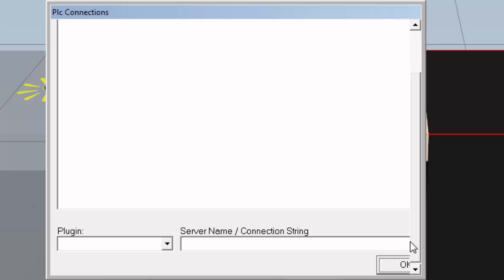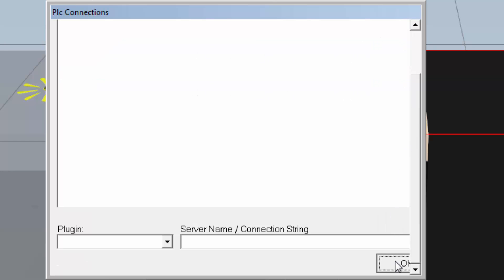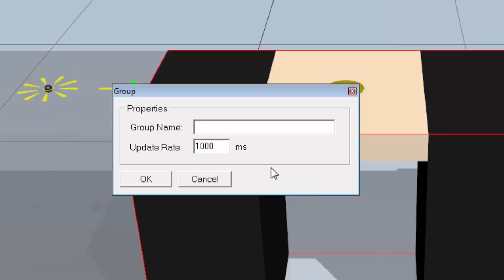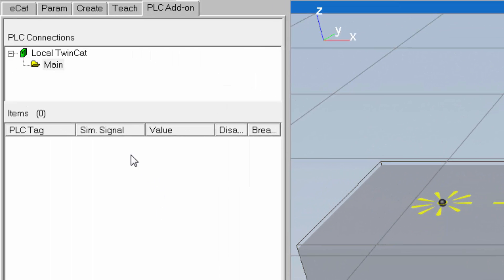I can manually type in the connection or select it from a list. I already have TwinCAT installed locally on my device, and there's the port 851. I'll scroll down and click OK. I'll give the connection a group name — I'll type 'main' — and set an update rate of 10 milliseconds, then click OK. You'll be prompted to map PLC variables to items in the 3D world, but we haven't done that step yet, so I'll close this out. Up at the top in PLC Connections, we are connected to the TwinCAT PLC.